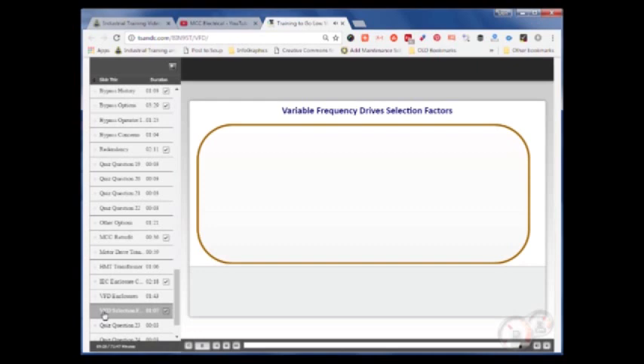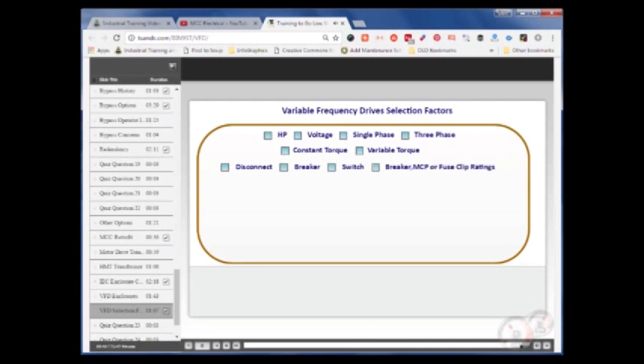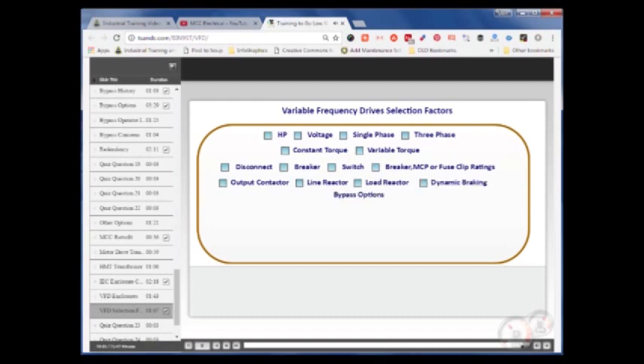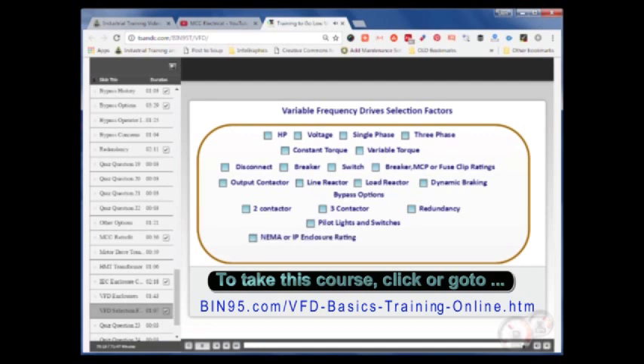Let's go through the selection factors that apply to variable frequency drives. You need to know the horsepower, voltage, and if the voltage is single phase or three phase. Next, you need to know whether it's constant torque or variable torque. Next, you will need to know if a disconnect is required, and if a disconnect is required if it is a breaker or a switch, and the current rating or fuse clip rating that applies. Next, you need to find out if an output contactor is required, if an input line reactor is required, or a load reactor, if dynamic braking is required, and then if bypass is required, is a two contactor or three contactor required, what are the pilot lights and switches required for the bypass operation, is redundancy required using two drives, then you need to know the NEMA or IP rating of the enclosure, and lastly, if any special boards are needed for interfacing with a network system or with an encoder.